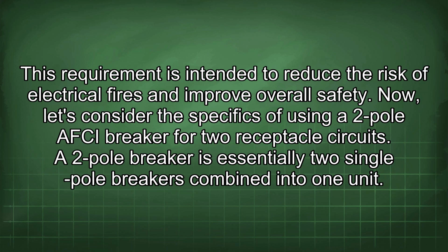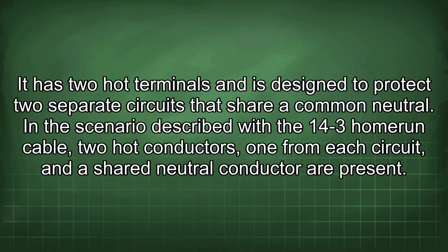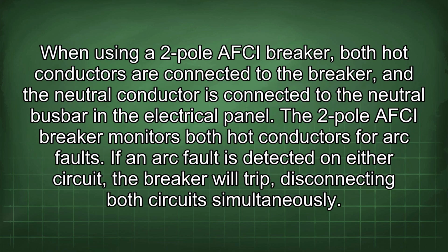Now, let's consider the specifics of using a two-pole AFCI breaker for two receptacle circuits. A two-pole breaker is essentially two single-pole breakers combined into one unit. It has two hot terminals and is designed to protect two separate circuits that share a common neutral. In the scenario described with the 14-3 Romex cable, two hot conductors, one from each circuit, and a shared neutral conductor are present. When using a two-pole AFCI breaker, both hot conductors are connected to the breaker, and the neutral conductor is connected to the neutral busbar in the electrical panel.